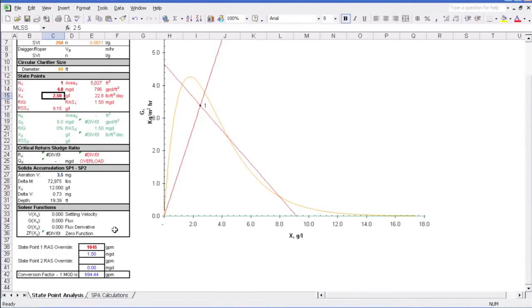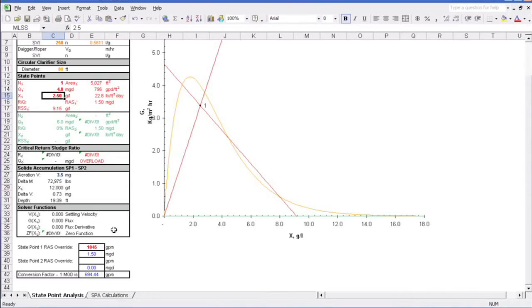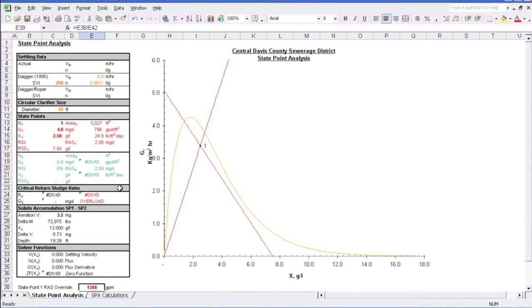Say we actually have a little bit more capacity in our RAS pumps and can turn those up to 2MGD. Well, does it help? Yep. As we discussed, increasing the RAS flow results in a steeper underflow rate line, and we're back in good shape. Good job. Crisis averted.